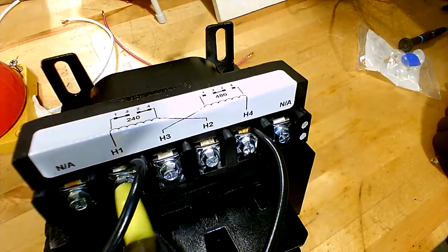You can't do that traditional way. So your jumpers are going to drop in like this. Loosen up the H1 and H3 and slide the jumper in behind there, and the other jumper goes in on H2 and H4 above the saddles. You can leave these wires flopping off. Go ahead and do that on camera, and I'll film you doing this.